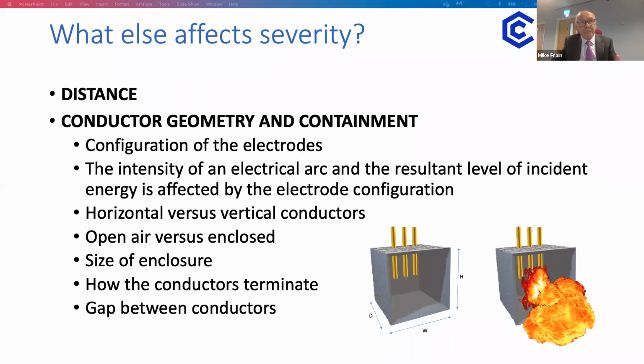Next is the conductor geometry and containment. Firstly is the configuration of the electrodes. The second is the intensity of an electrical arc, which is a result of the level of incident energy affected by that electrode configuration. It's also that horizontal and vertical conductors can create increased or lower amounts of thermal energy.